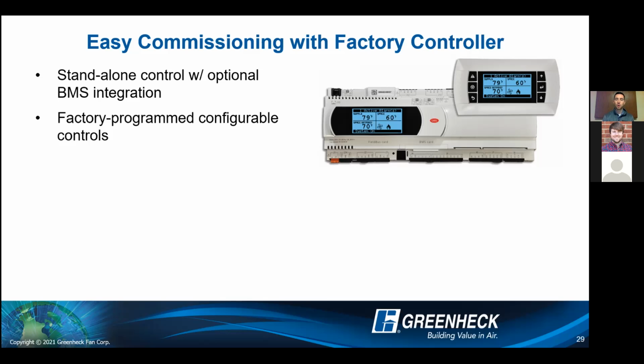Let's just say down the road, all of a sudden something happened and you want to change it to constant volume supply fan control. Instead of getting a big factory update or program update that you need to do on that controller, all you have to do is get into that control screen, change that supply fan from duct pressure over to constant volume, and then that screen will come to the surface. So all of that logic is built in that controller. It's just really what's at the surface configured at that time.